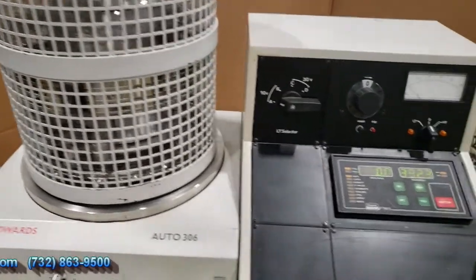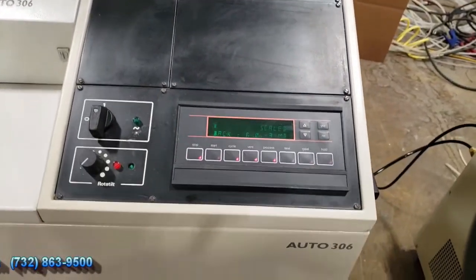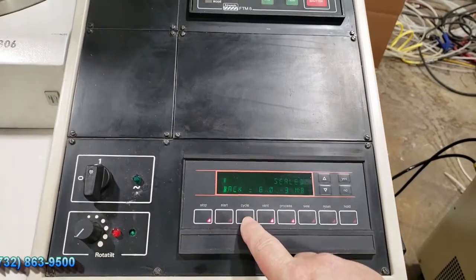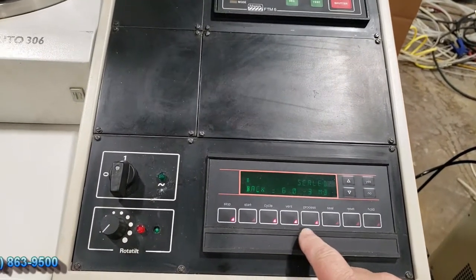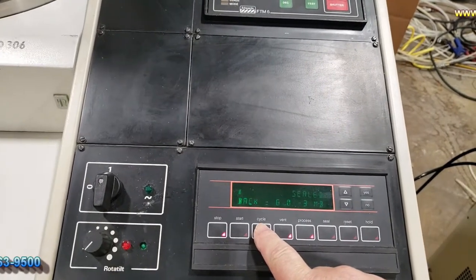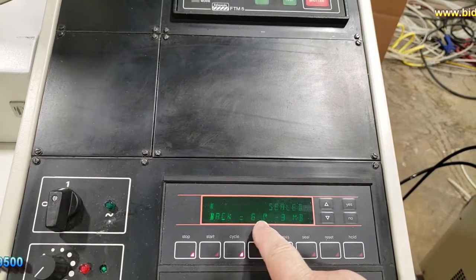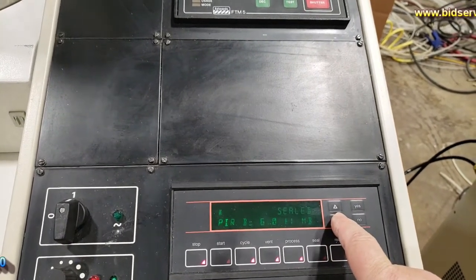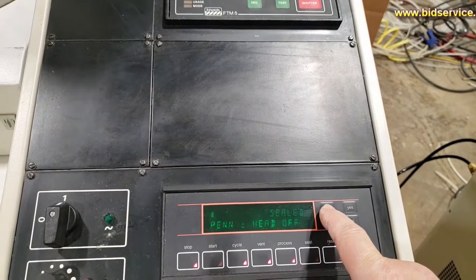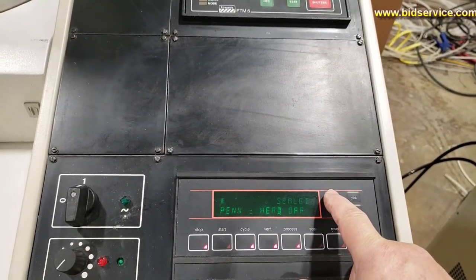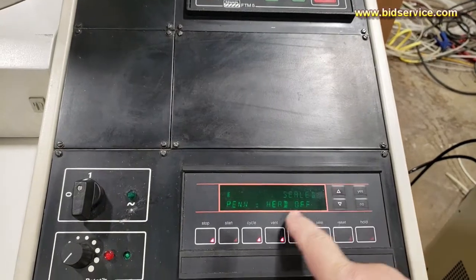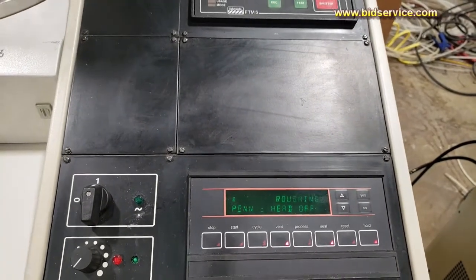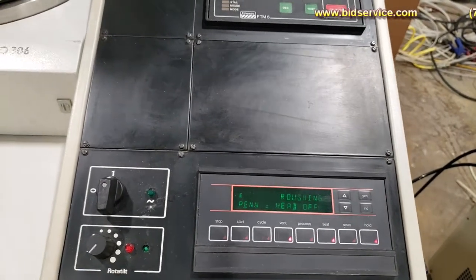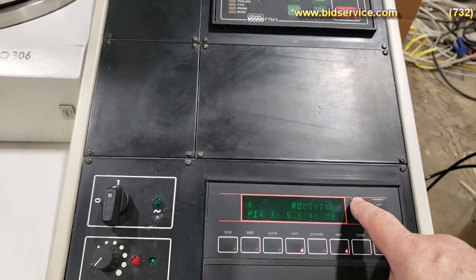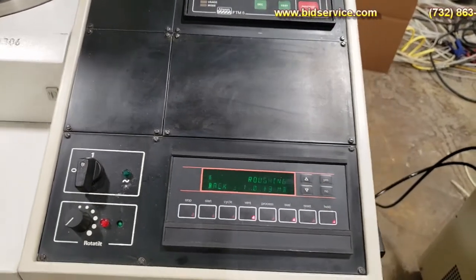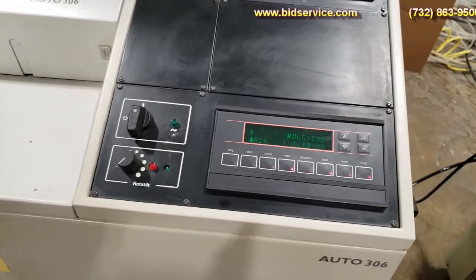Alright, and to pump down the system, you just go back to the pump controller. You'll have the 3 or 4 lights lit up, and then basically you just want to hit the cycle. In this gauge right here, you see this is your backing pressure. If I go down, it will give you your chamber pressure and then your penning, but penning's not on since it's not under high vac. So basically you're just going to hit the cycle button and it's going to go through the process.